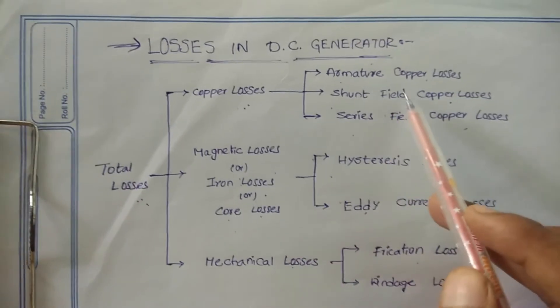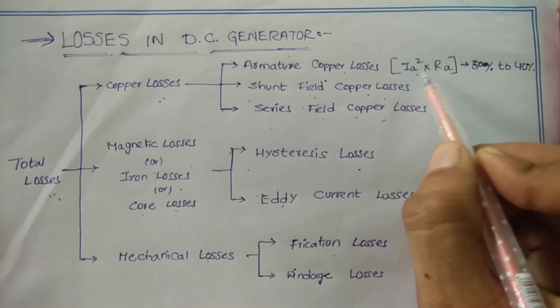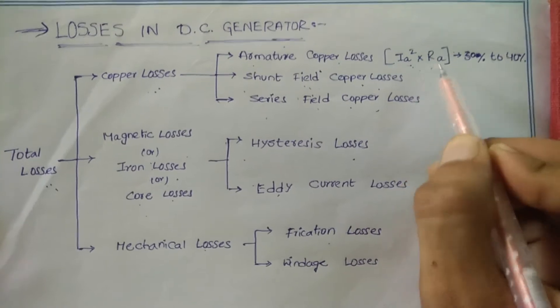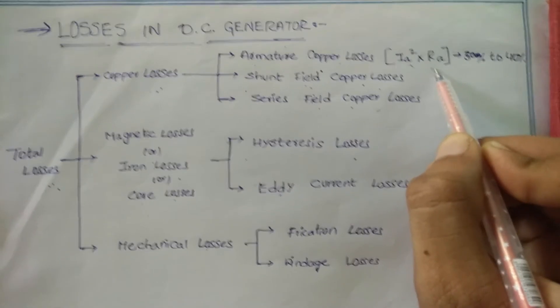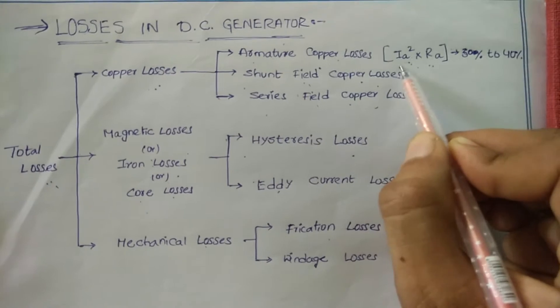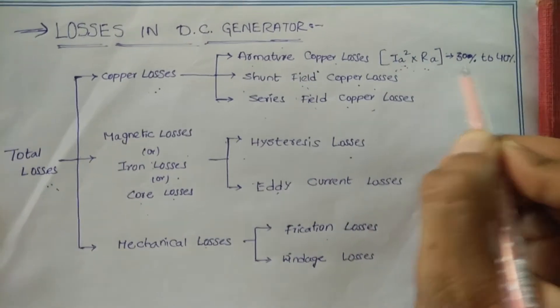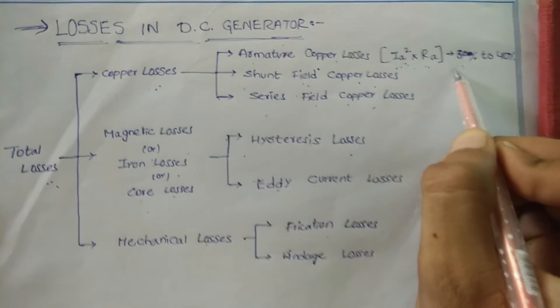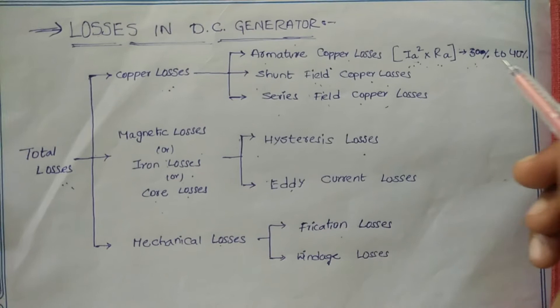The first type is armature copper losses, denoted by I² × Ra, where Ra is the armature resistance and I is the armature current. These losses account for about 30 to 40 percent of the full load losses, meaning 30 to 40 percent of total losses.